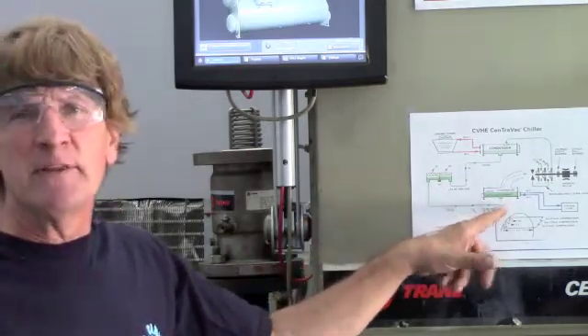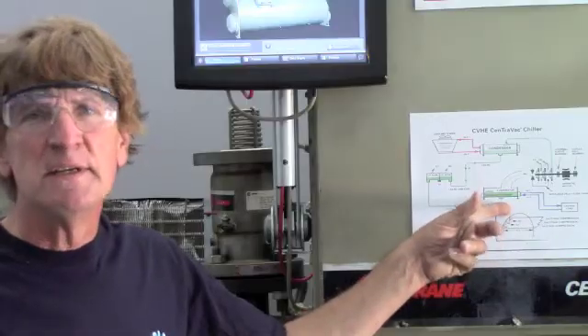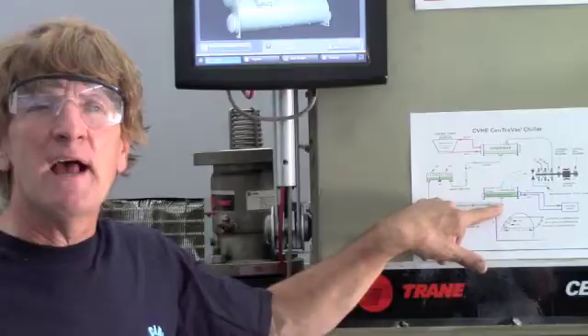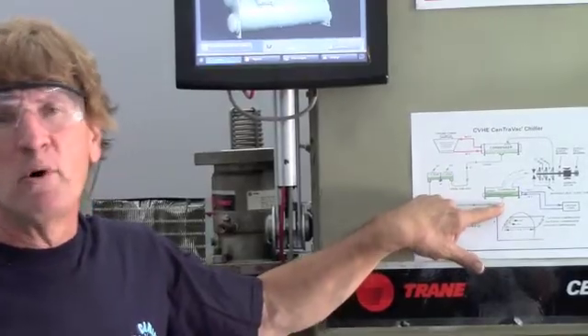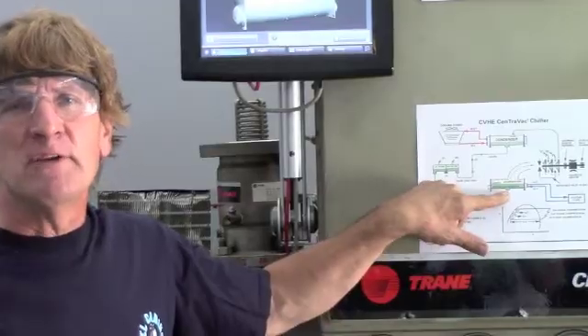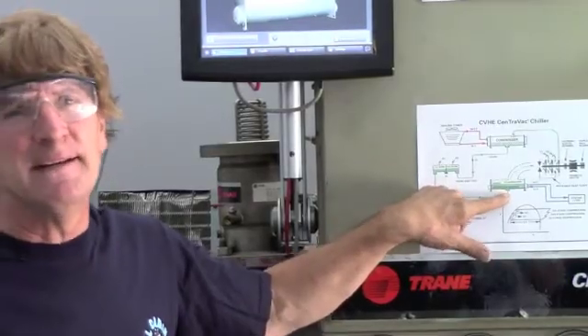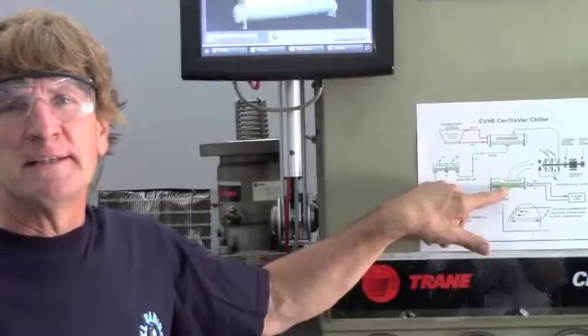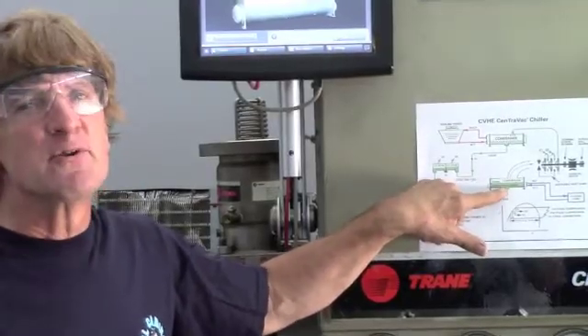The refrigerant comes down as a liquid into the evaporator. That liquid covers the tubes. Right in here where it goes in, we have a restrictor or an orifice. That allows it to drop from a relatively high pressure — maximum 15 pounds — to a vacuum: 18 to 20 plus inches of vacuum, depending on the refrigerant and the application.